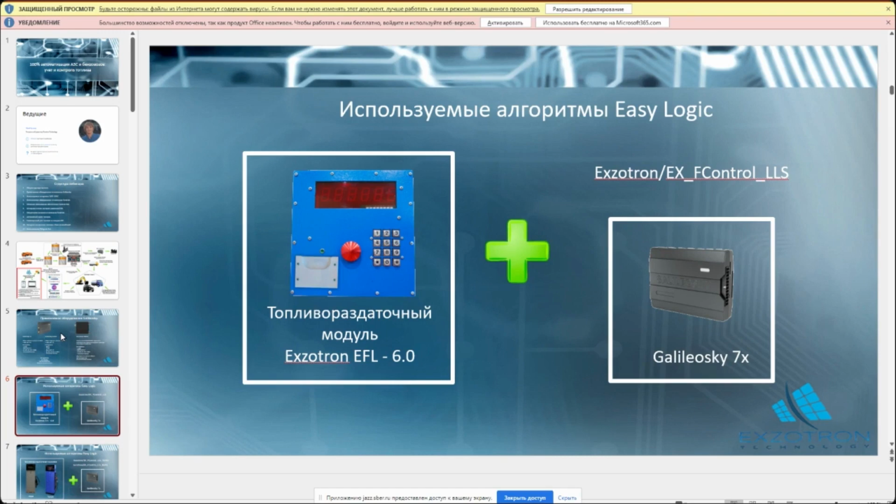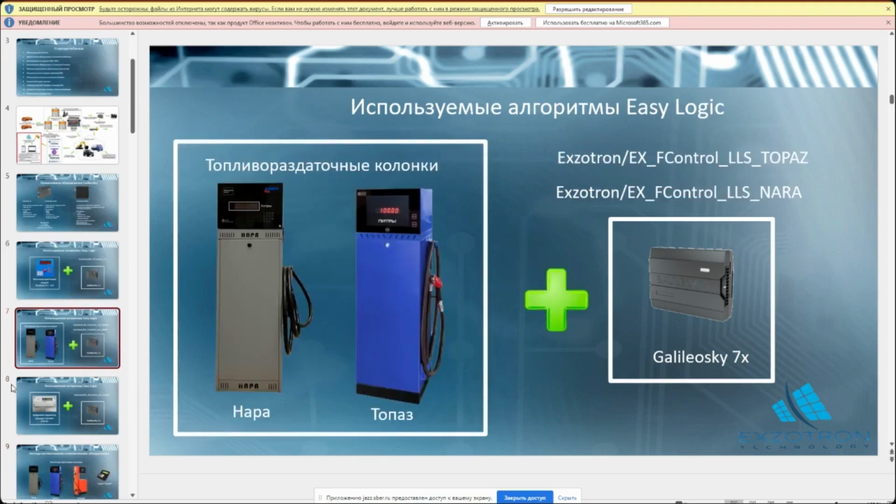When utilizing algorithms, interaction occurs solely via RS-485, although there is a configurable discrete pulse output. This output can generate 110 or 100 pulses per liter, allowing for connectivity in any location. All configurations are performed via the keyboard. In addition to pulse outputs, the module also transmits a cumulative total counter, which the operator has the ability to view on the screen. When working with limits, it is possible to display either one or another set of limits on the screen for better visualization.